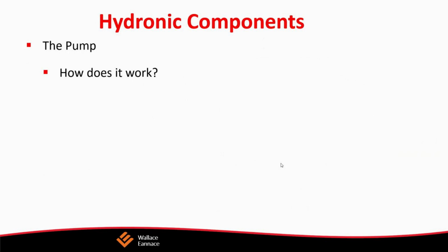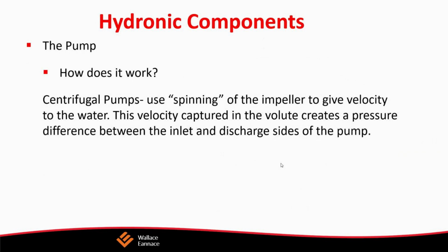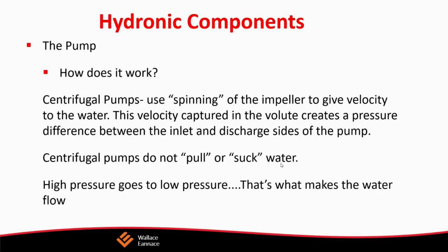Let's talk about hydronic components. Now, we have a boiler. We consider the boiler. We consider the size of the boiler. We've already determined that most of the time we need less boiler, but we have to design for that maximum point. So we want to consider using a modulating boiler, but with that, we're going to have a whole variety of hydronic components. Key to that is the pump. Let's consider what it does, how does it work, how do we size it, and what are the options in pumps?